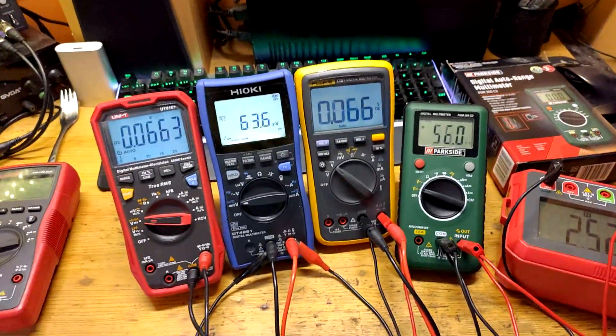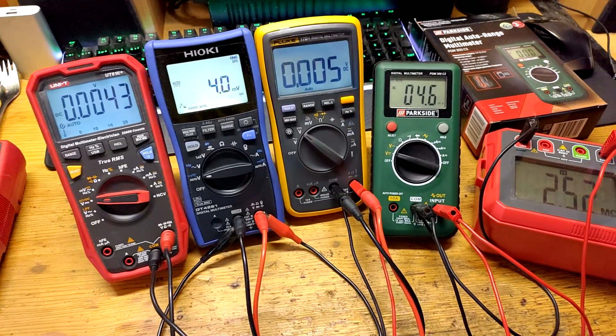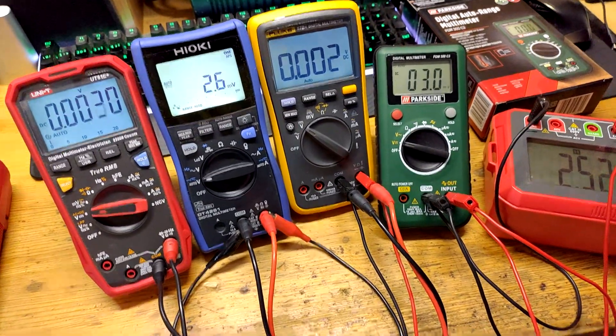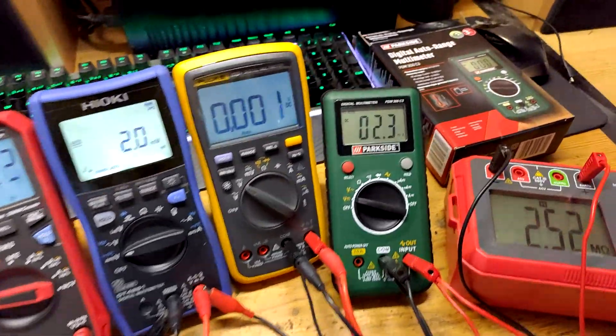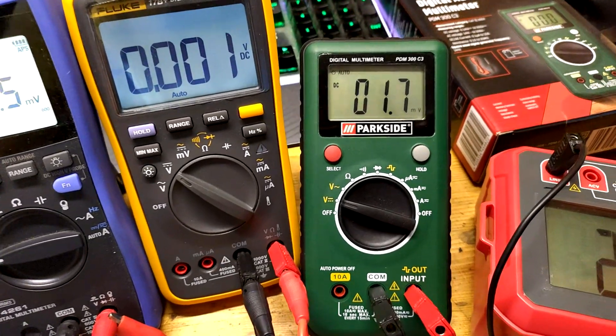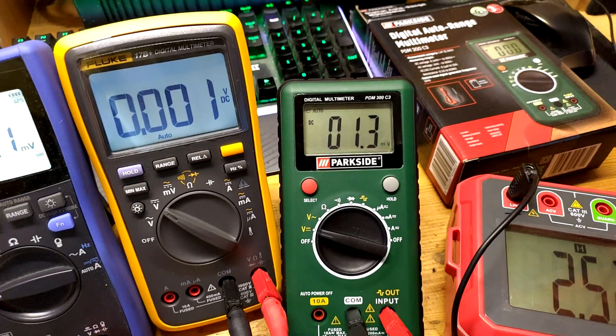So if someone would be so unfortunate to measure voltage between phases — to, for example, determine whether it's live or not and he can begin work — and he measures zero volts on the Parkside, the multimeter says zero volts and he begins working on the device. And boom, he is dead.